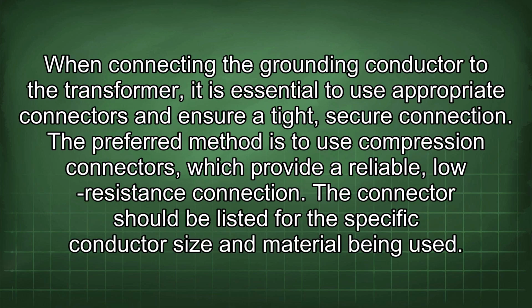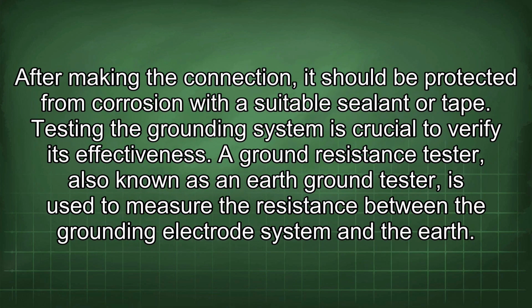When connecting the grounding conductor to the transformer, it is essential to use appropriate connectors and ensure a tight, secure connection. The preferred method is to use compression connectors, which provide a reliable, low-resistance connection. The connectors should be listed for the specific conductor size and material being used. After making the connection, it should be protected from corrosion with a suitable sealant or tape.